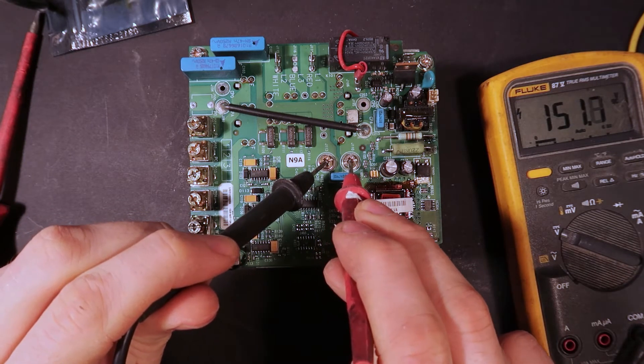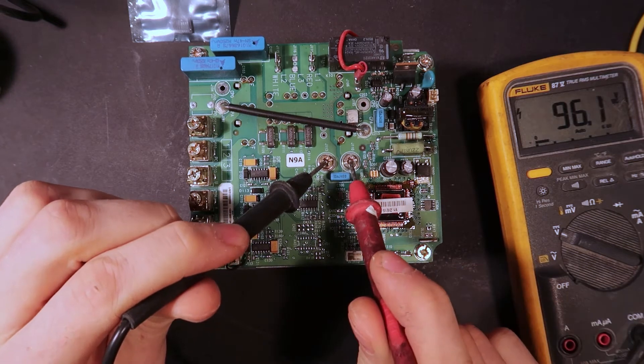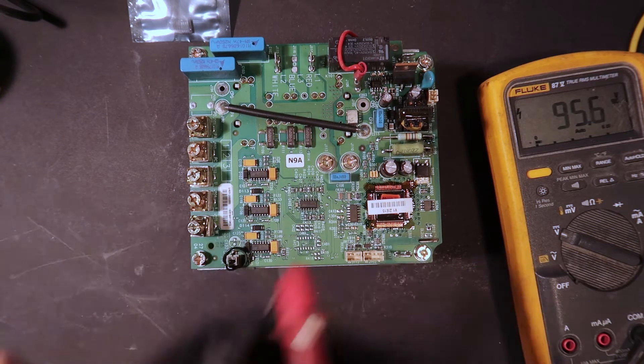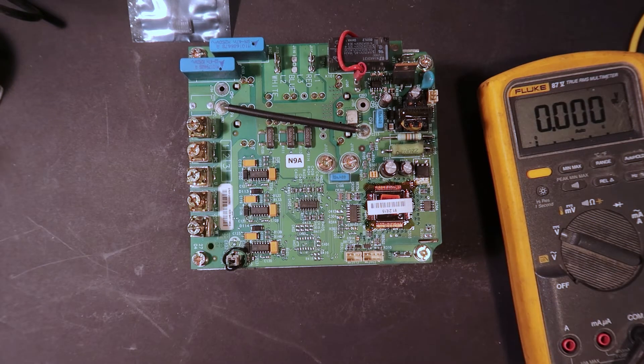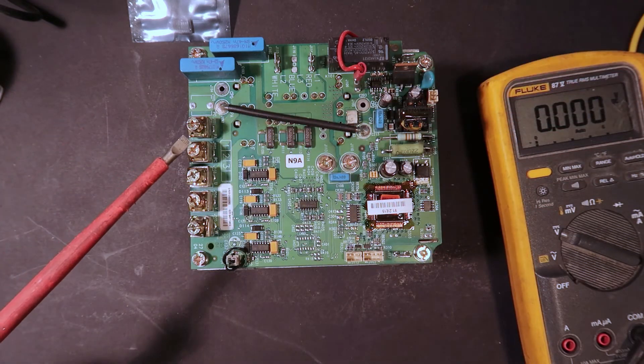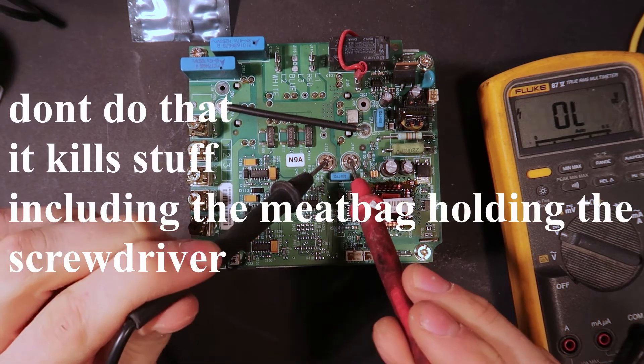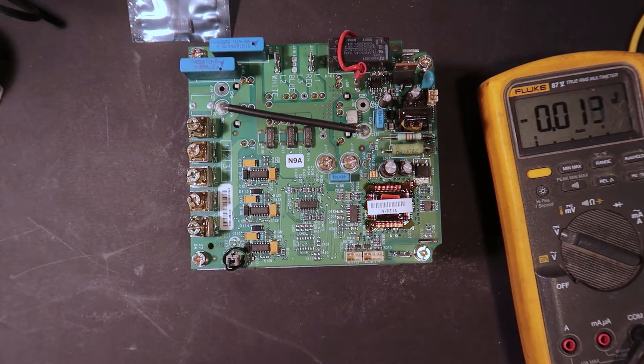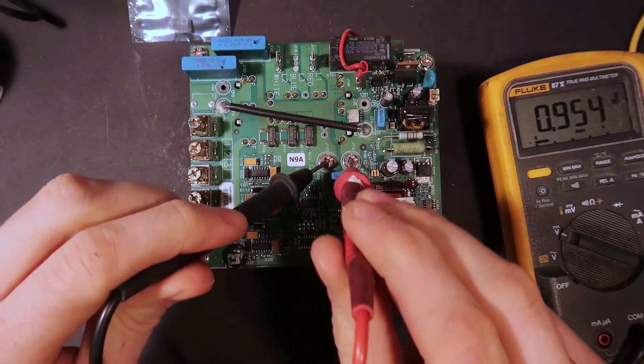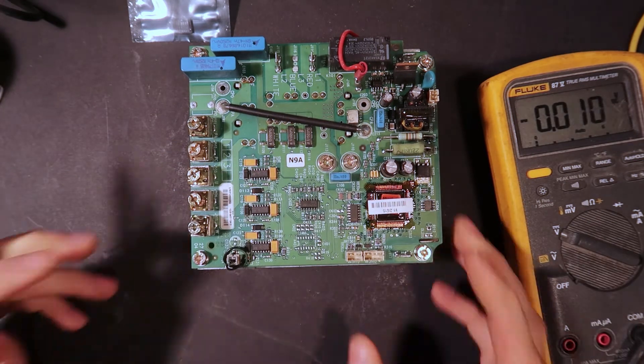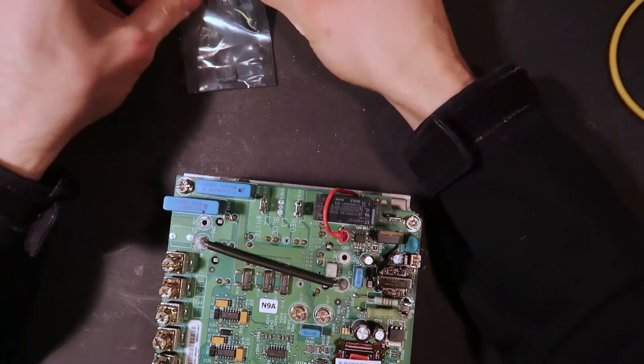152 volts DC. Another couple minutes went by, we're at 95 volts DC. So we take our little electrical screwdriver here and let's just zap that out. It was a bit more violent than I expected. 15 volts. We're basically at zero, so now we can start working.